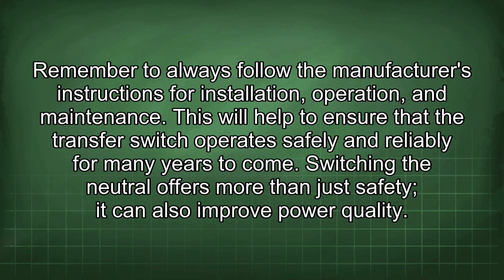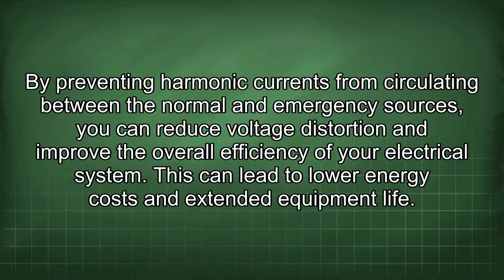Switching the neutral offers more than just safety, it can also improve power quality. By preventing harmonic currents from circulating between the normal and emergency sources, you can reduce voltage distortion and improve the overall efficiency of your electrical system. This can lead to lower energy costs and extended equipment life.